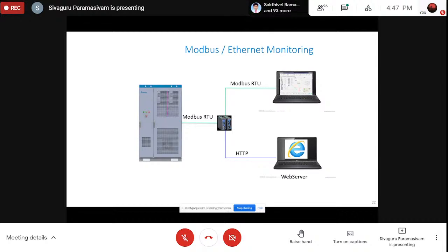So that's a glimpse about the communication. You can see there is Modbus RTU, and then you can ask why there is an HTTP coming to the web server. That is a different protocol. That could be one of the questions from this slide. But you can also see a component which is a communication converter. In the market, we use communication converters, which are similar to Google Translator. I can type your language and then understand what you are speaking. Similarly, we use protocol converters because these components are used in different countries, and different manufacturers have their own protocol. So we ensure that communication converters are available to map and match all the communications that we do.